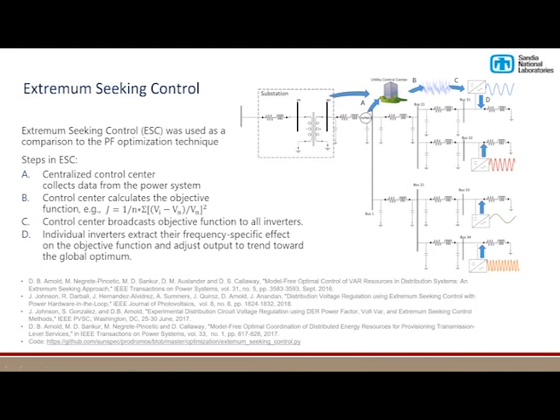It's a relatively low periodicity in terms of the ripple, maybe a period every 30 seconds or so. Each of them has a different frequency, and because of that, you can extract their influence on a globally transmitted objective function. In our case, since we didn't have the ability to broadcast that objective function, we pulled in data from the field and calculated the objective functions locally, and then sent each of the inverters the reactive power set points they needed using a power factor set point.